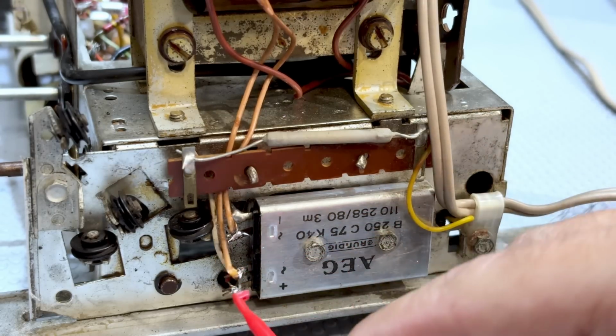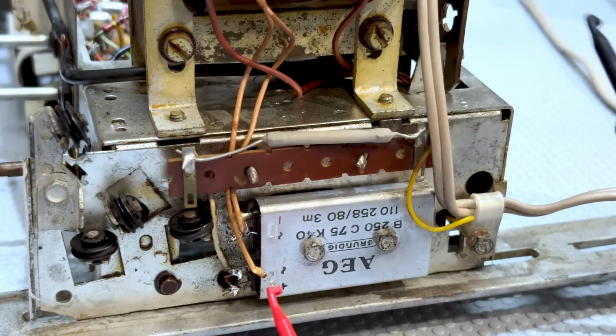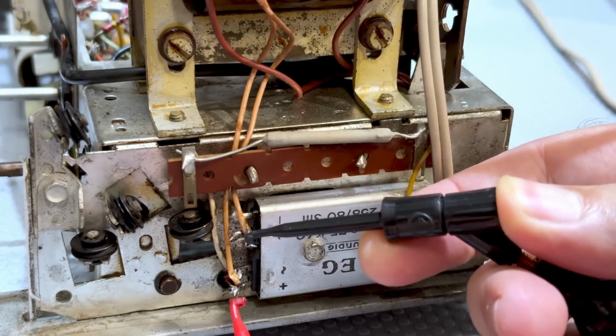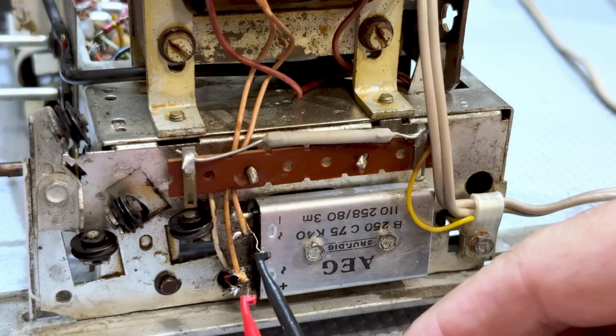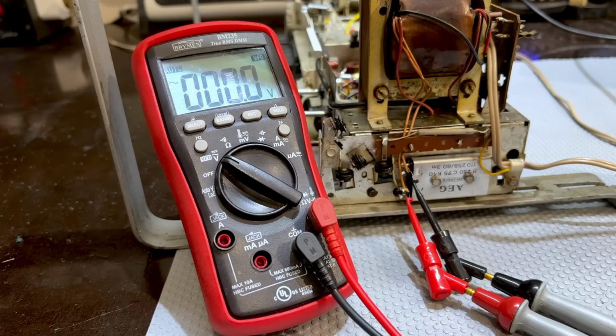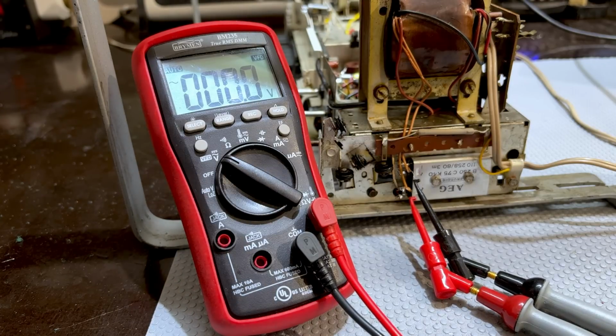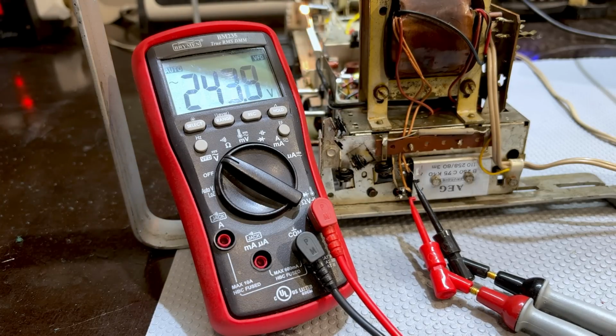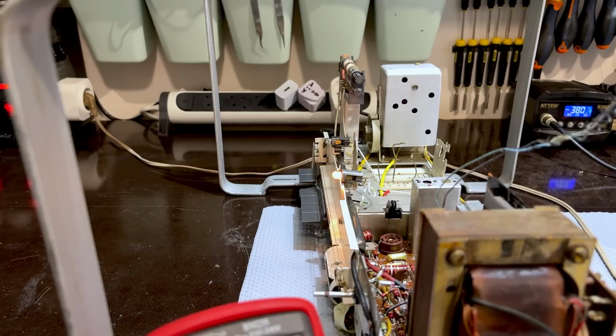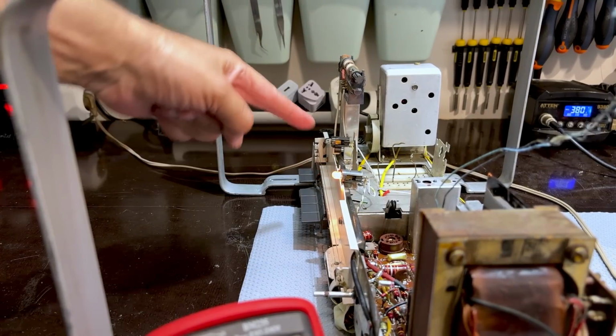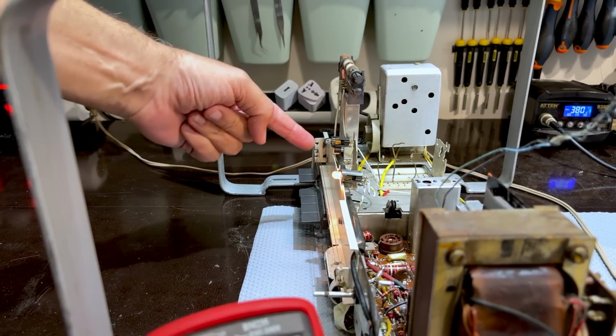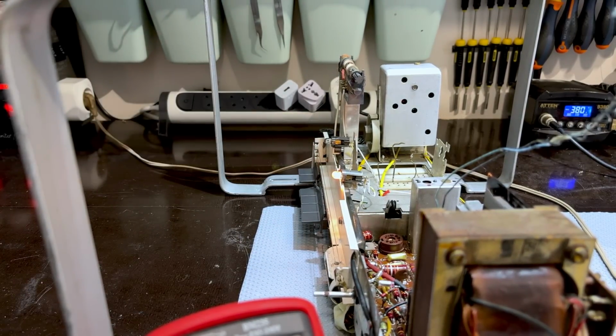Now I just want to test what voltage I get on the secondary of the transformer. Got to be very careful because there's high voltage here, or we hope there is. We set the meter to AC volts - yep, we're getting a high voltage, near 240, that sounds about right. The other thing I've noticed is that one of the dial lights is on, the other one is burnt out and darkened, so one is on, meaning our heater supply is working as well.